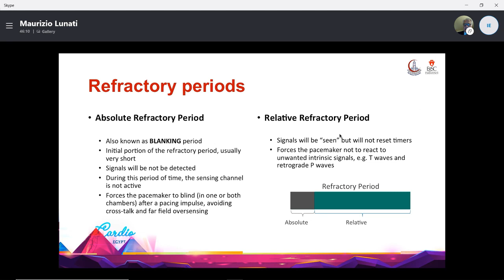Obviously, this is extremely important because it forces the pacemaker to be blind in one or in both chambers after a pacing impulse, avoiding two things that could be very dangerous, which are crosstalk and far-field oversensing. And the other important refractory period is what we call the relative refractory period, which is longer than the absolute refractory period. In this time, signals will be seen, but they will not reset timing. What is the use of this relative refractory period? It forces the pacemaker not to react to unwanted intrinsic signals that could be T waves and retrograde P waves.